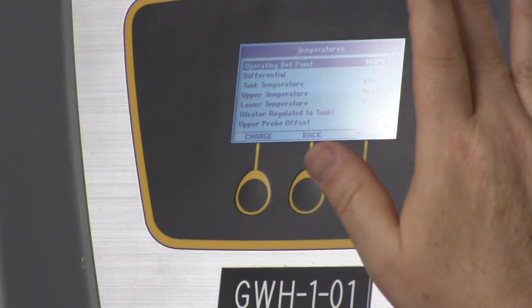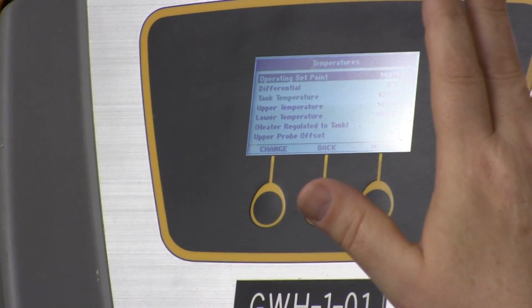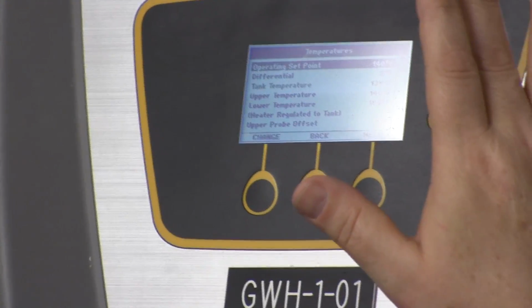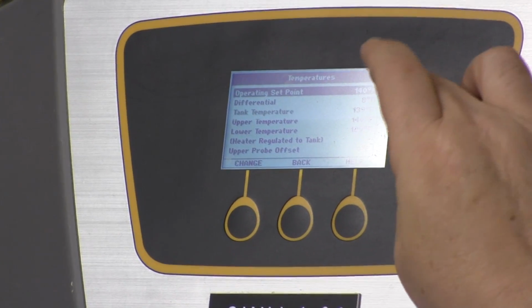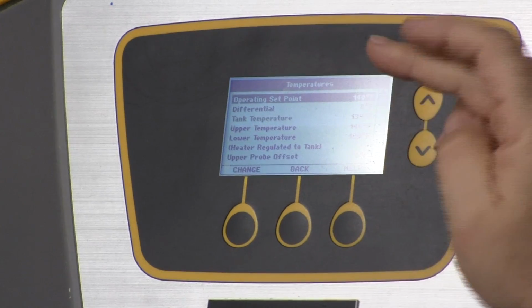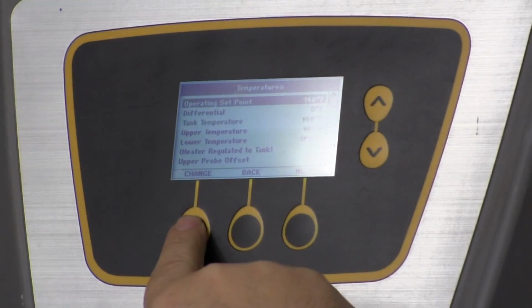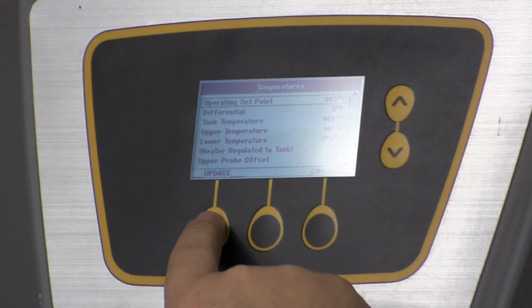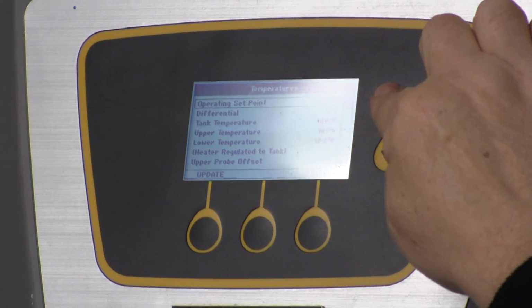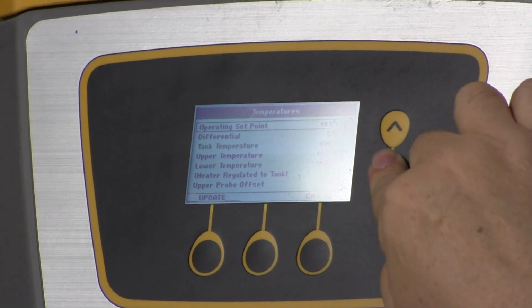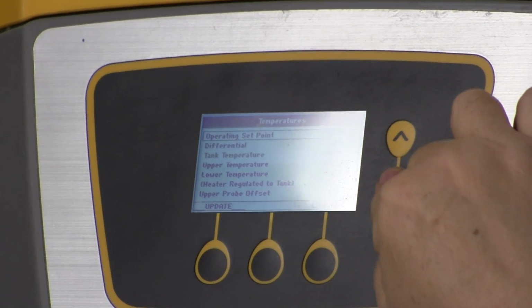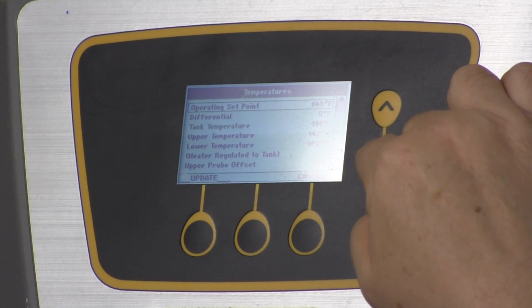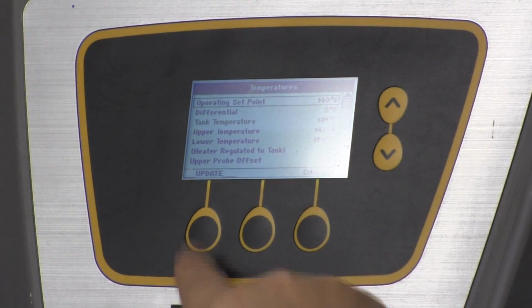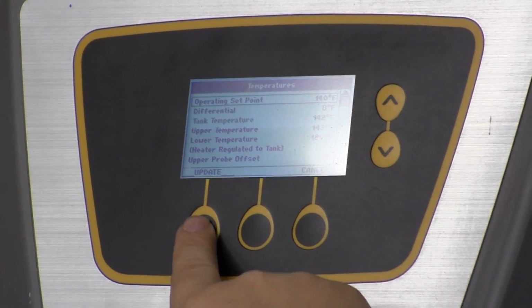Does everyone get that concept? So, the mixing valve is right here around the corner. So that's allowing only 120 to go out to the units. The next thing on here is a differential. And if you were going to change any of these, you'd hit change. Say you want to hit change on the temperature. Now I can move the temperature up and down. Okay? And we do have a kitchen loop off of this, so you only want to set that to 140.